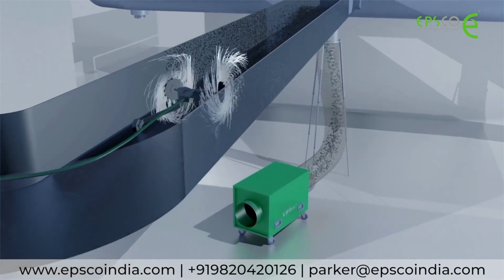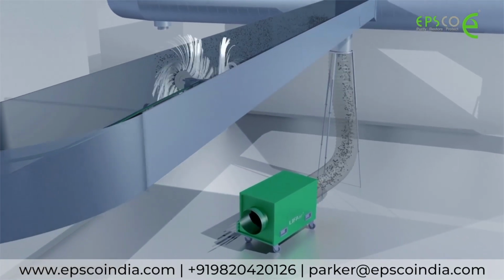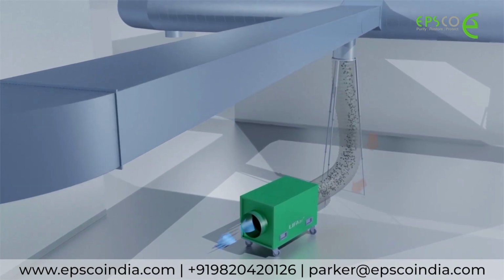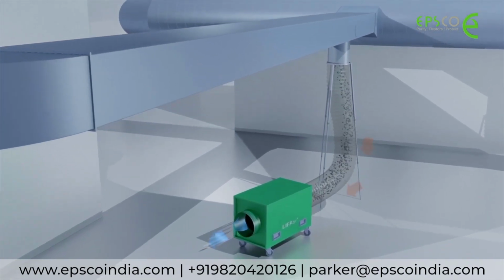being that you have proof of the entire system from one end to the other has been cleaned to spec, and that spec is all non-adhered dust. By non-adhered I mean which is not stuck on the duct like paint or corrosion, has been removed. And if there are any defects within the system, if there is any corrosion, that also can be identified, located and fixed. So that's why robots are used.